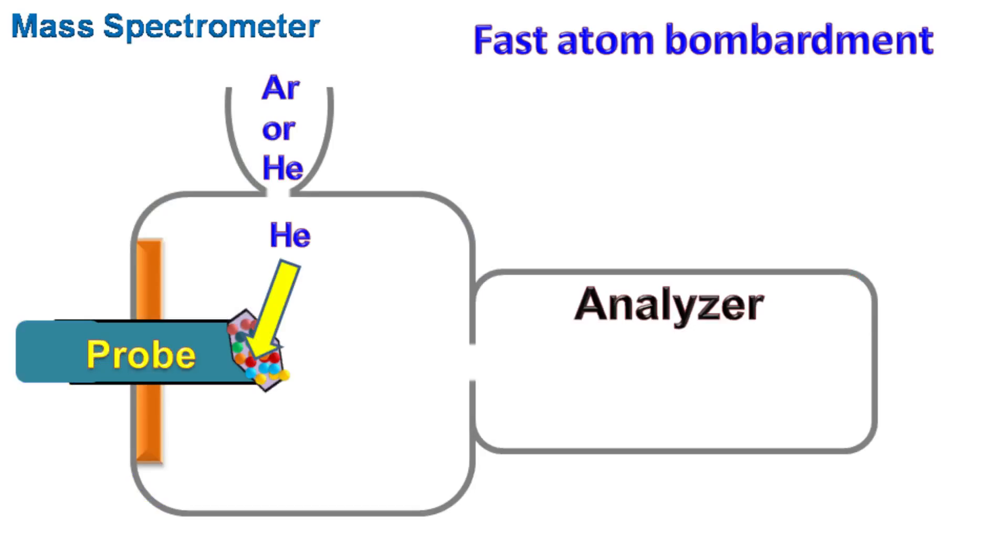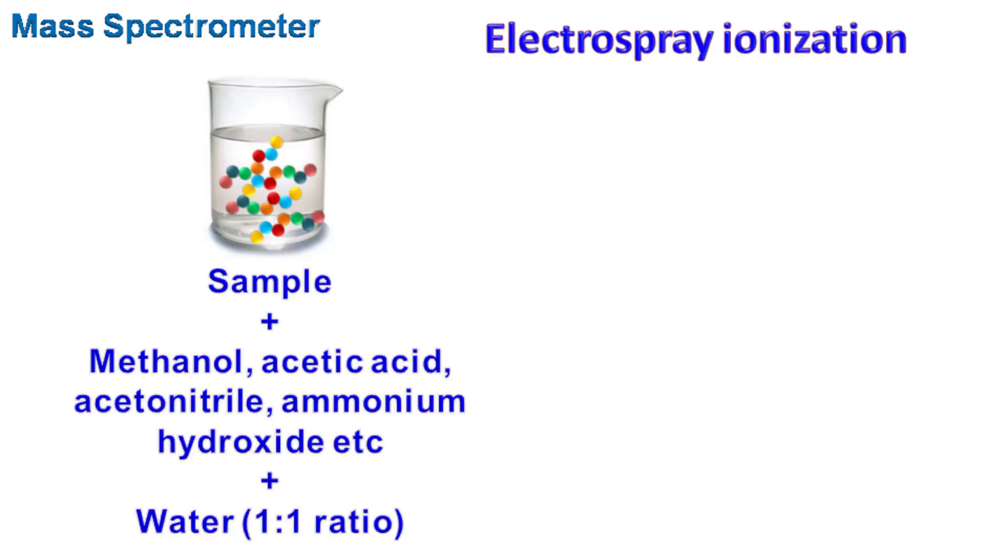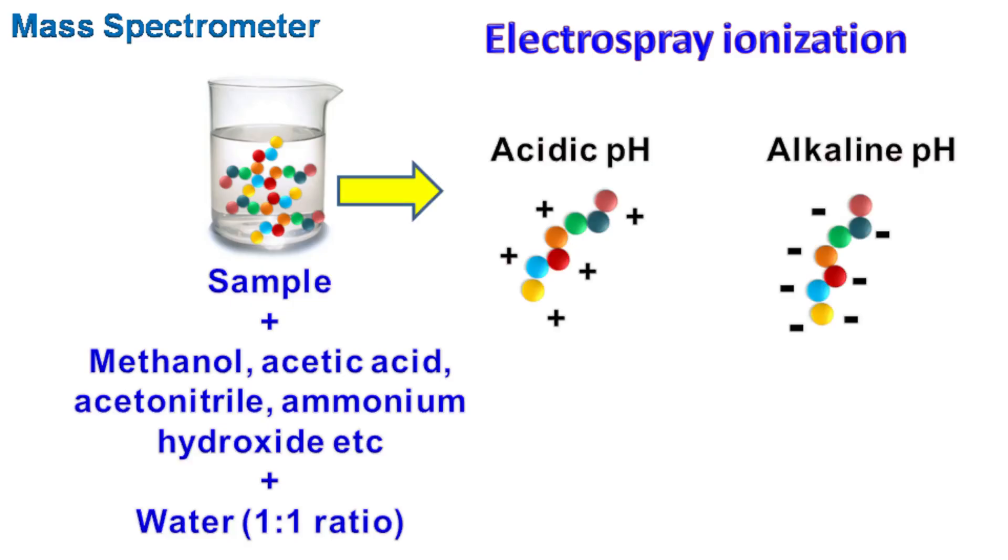Electrospray ionization: In this method, solution of sample molecules is spread in an electric field to produce ions. This method is popular for analysis of biomolecules such as proteins and DNA. The sample molecules can be mixed with solvents such as methanol, acetonitrile, acetic acid, formic acid, ammonium hydroxide, etc. along with water in one-to-one ratio. Depending on the pH of solution, the sample molecules can either have positive or negative charge.